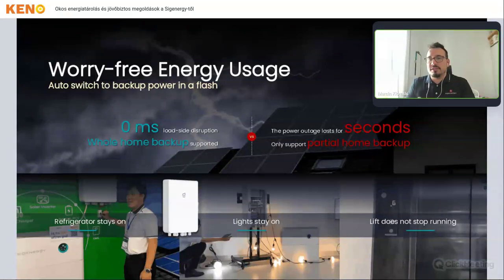But our product was targeting some C&I and especially bigger C&I scenarios. In such a case, there is a problem when they're willing to have like 50, 100 kilowatt backup power. In our system it is very simple because we have exactly one element which is disconnecting the system from the grid, and you can have numerous inverters working in parallel, so we can provide the backup feature. And what is really astonishing is the 0 millisecond backup time, because the inverter is strictly connected to the loads, and generally in the low voltage ride through function, it's just providing the feature to keep the whole system stably working, and the gateway is just the element which is disconnecting from the grid.